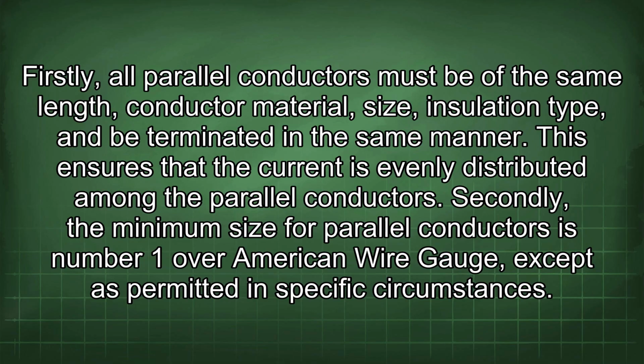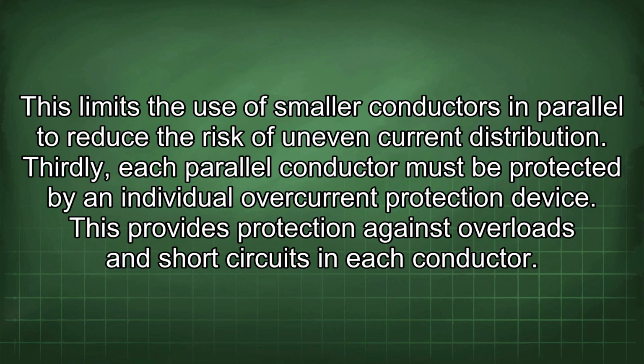Firstly, all parallel conductors must be of the same length, conductor material, size, insulation type, and be terminated in the same manner. This ensures that the current is evenly distributed among the parallel conductors. Secondly, the minimum size for parallel conductors is number 1/0 American Wire Gauge, except as permitted in specific circumstances. This limits the use of smaller conductors in parallel to reduce the risk of uneven current distribution.